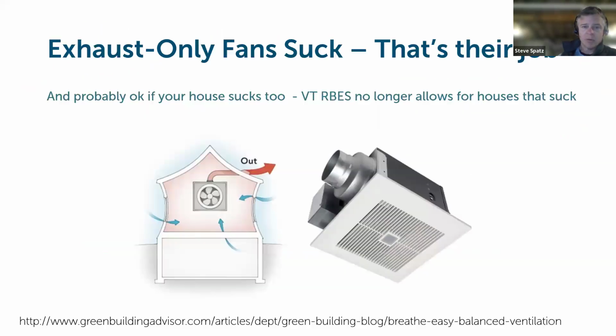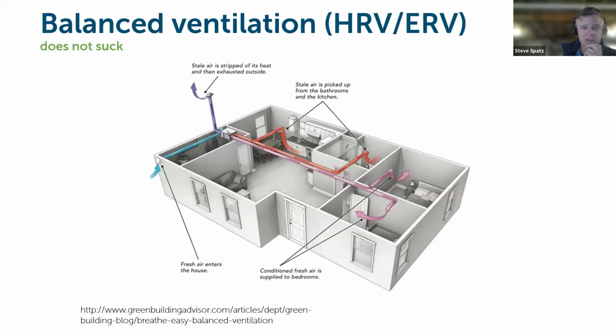But what we're doing here with a balanced ventilation system is not just relying and hoping that the building envelope's going to leak to get fresh air exchange. We're actually creating a balanced system where you're pulling in fresh air from the outside and exhausting stale, humid air and other pollutants from inside the house at an equivalent rate. So there's a balance in the system here. You're not depressurizing the building. You're distributing air throughout the entire building.